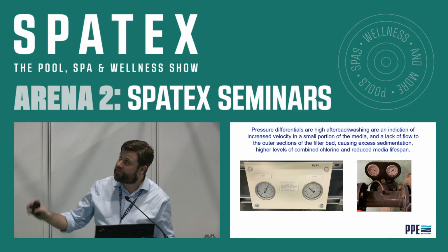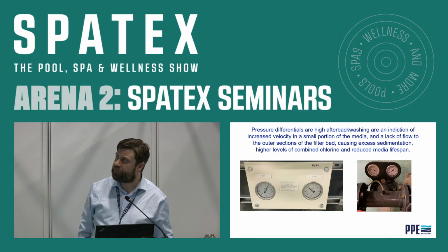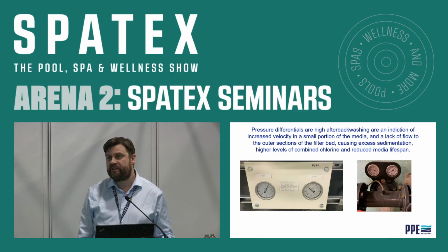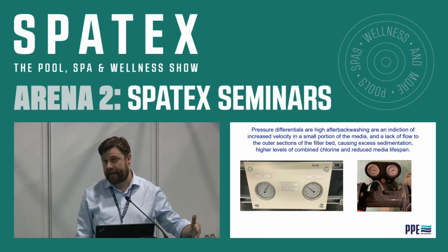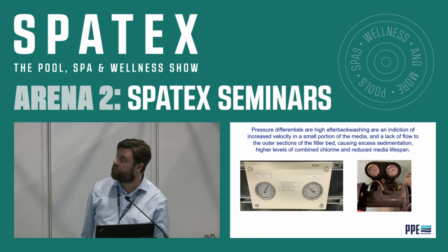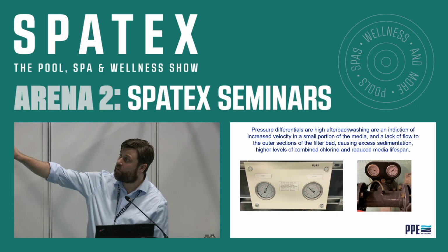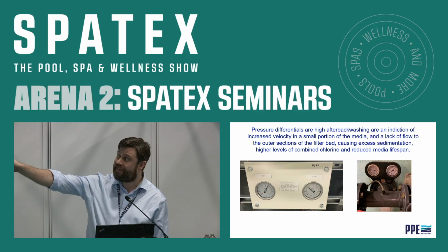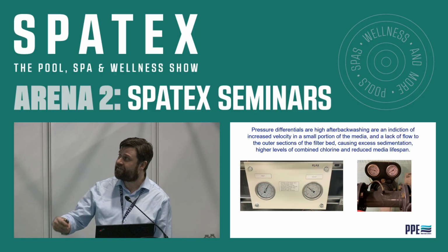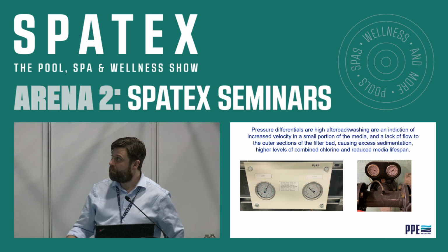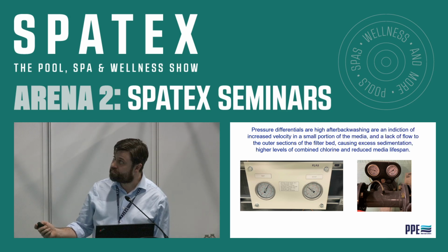If you do backwashing and following the backwash, we see these pressure gauge differentials still being very large. That is another indication that there's still a lot of resistance within the media bed even after we've done that backwash. And that's the same with both of these examples. Okay? Obviously, the one on the right is quite a bit more pronounced than the one on the left, but this is still not acceptable. Okay? It's still too great a difference, especially after just conducting a backwash. And if we can't backwash the filter, we can't get rid of the pollution. If we can't get rid of the pollution, it's a food source for the bacteria to feed on. Biofilms will form, and then it's just downhill from there.